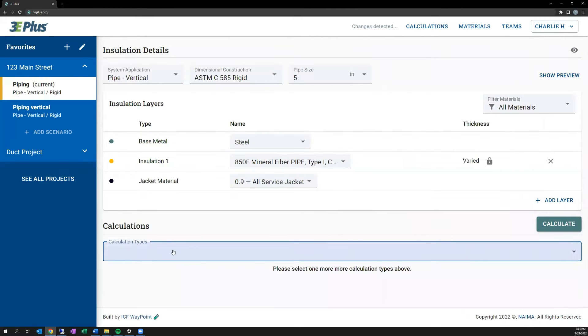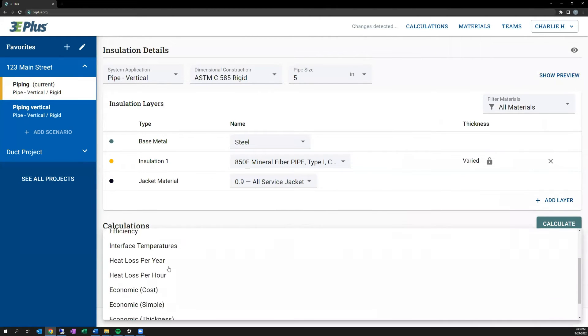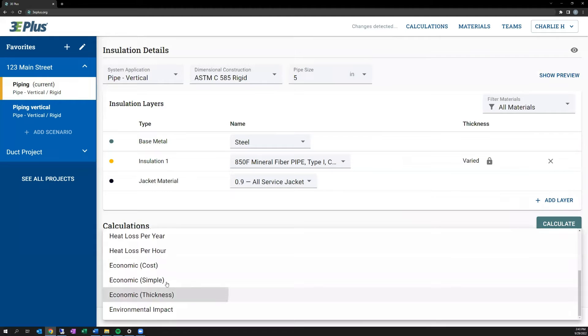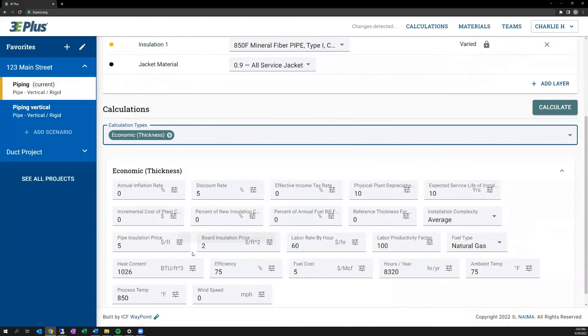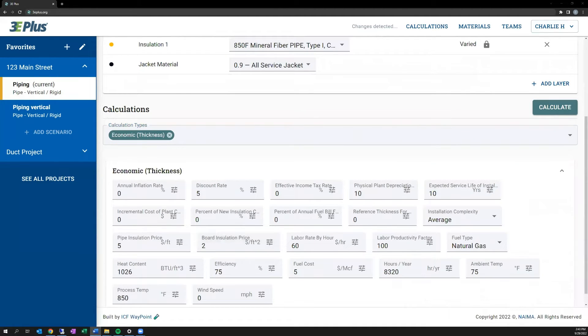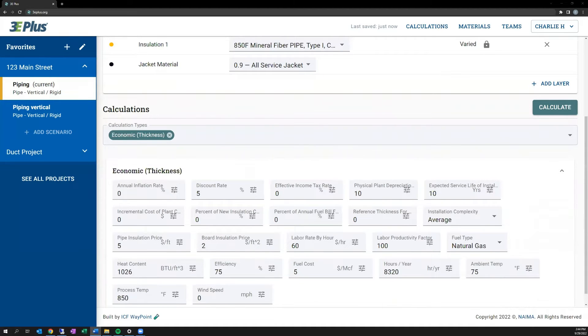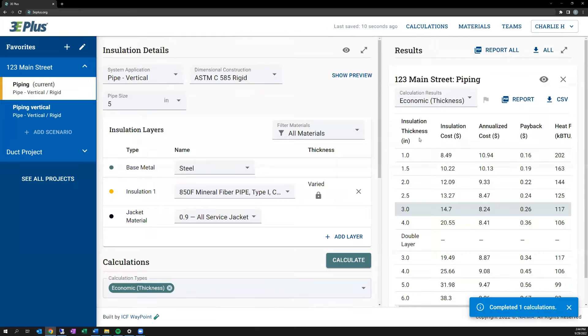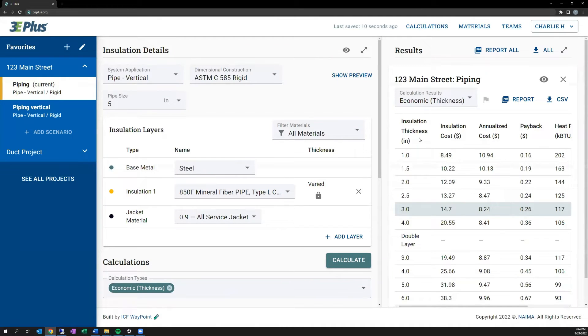Lastly, at least in terms of economic calculation, is the economic thickness calculation. It takes it one step further beyond that simple payback calculation by projecting out energy cost savings over time, which needs to take into account factors such as inflation, the discount rate, the expected lifespan of the installed insulation. And if you hit the Calculate button for this one, what it will do is that it will highlight the most cost-effective thickness of insulation that provides the combination of the lowest install cost with the highest estimated savings over the life of the insulation.